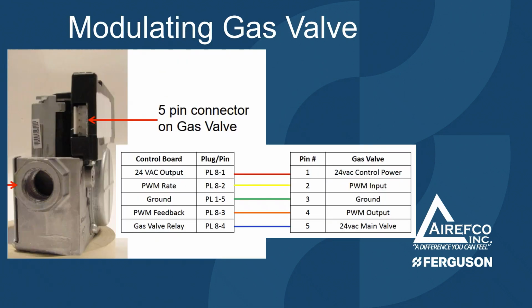Many modern furnaces now have a modulating gas valve and usually have a 5-pin connector to the gas valve. Through this 5-pin connector, the gas valve receives various signals to make sure that it operates correctly. You can get the values for each pin from the manufacturer of the gas furnace.